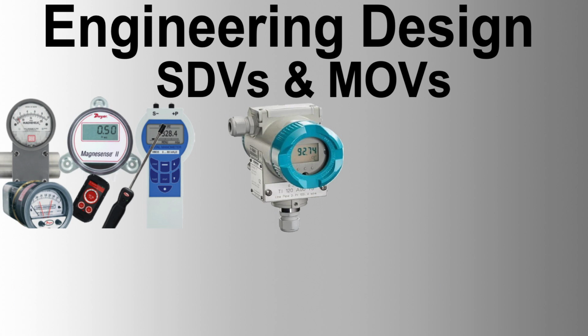The design of the actuator assembly shall consider the effect on the valve actuator of being left open-closed for long duration prior to operation and the effect of high-temperature service. The torque thrust characteristics of the actuator in its line application, including static and dynamic pressure effects, shall be compatible with the valve manufacturer's quoted torque thrust curves, taking into account the size of the valve and valve stem characteristics.